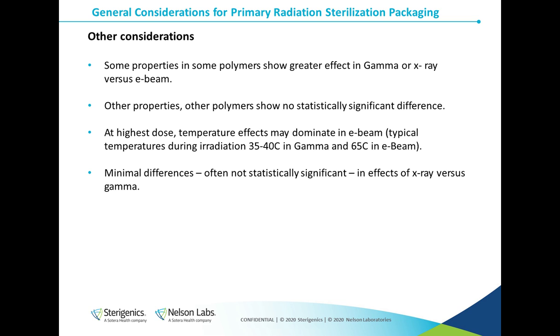Some other considerations for your sterilization process and sterilization packaging. Some properties in some polymers are more impacted in gamma or X-ray radiation versus E-beam, whereas other properties show no statistically significant difference between irradiation modalities. So, depending on what you are using for your packaging material, it may or may not be important which sterilization mode you are using with respect to material effects. In a prior slide, I showed an aluminized pouch, for instance, which would probably not show significant material effects in any of the radiation modalities.